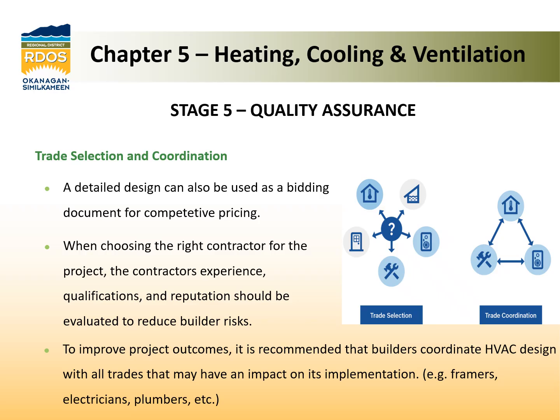So the design is done, everybody's happy, and we get to the point where it's starting to be installed. This is stage 5, the quality assurance stage. It's not enough to have successfully completed the discovery, performed the load calculations, and designed the optimum HVAC system, all coordinated with an effective IDP process. None of it will mean much if the installation isn't executed to meet the design intent or has been done with poor workmanship. The first step to continuing to a positive outcome is choosing the most appropriate installation contractor.